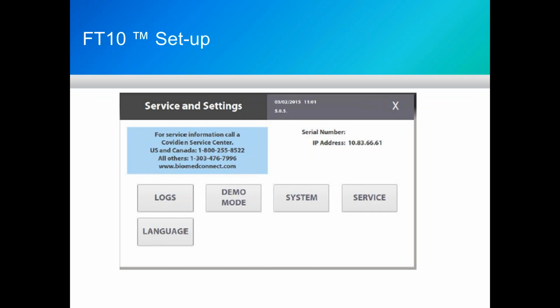Now, you saw me during the REM test push the little tool button on the bottom right center, if you will. And when you press that button, this comes up and gives you some options. So we have the demo mode, and that's where we used to do a lot of our testing with the Triad. The only thing that we really had to go into service mode for was the LigaSure testing. So we did all our monopolar, all our bipolar tests in demo mode, and we'll do the same here with this unit. When you go to Valleylab mode, that would be done in the service mode, as again, LigaSure is still done in service mode.